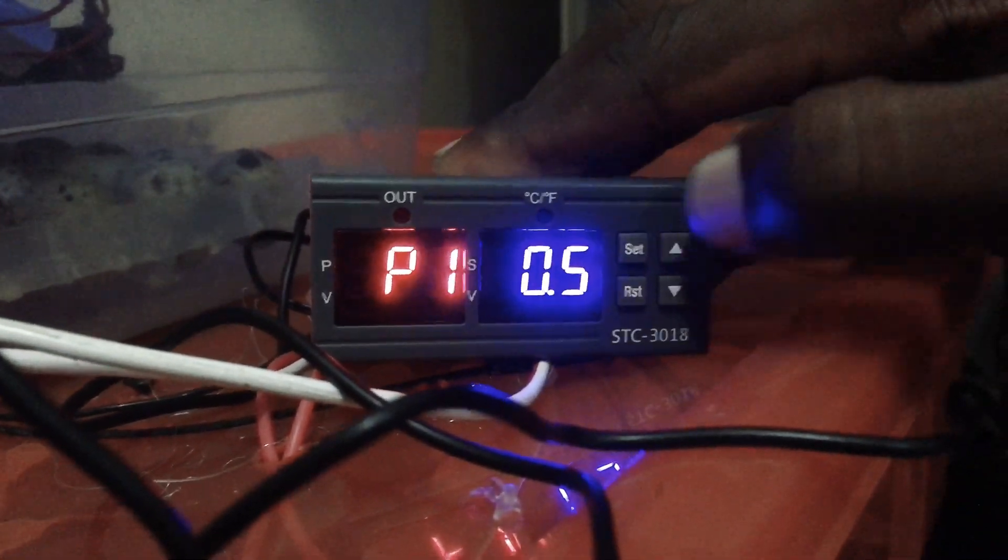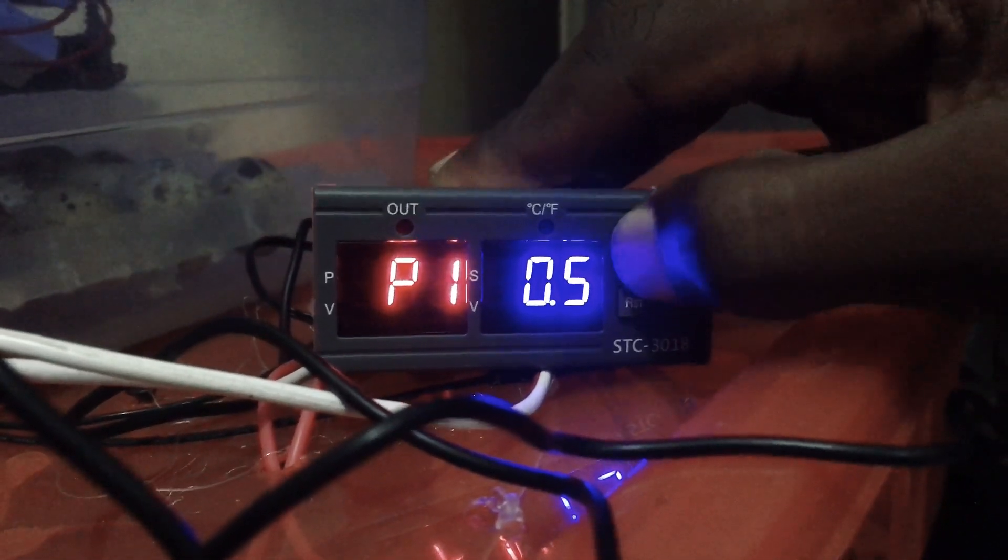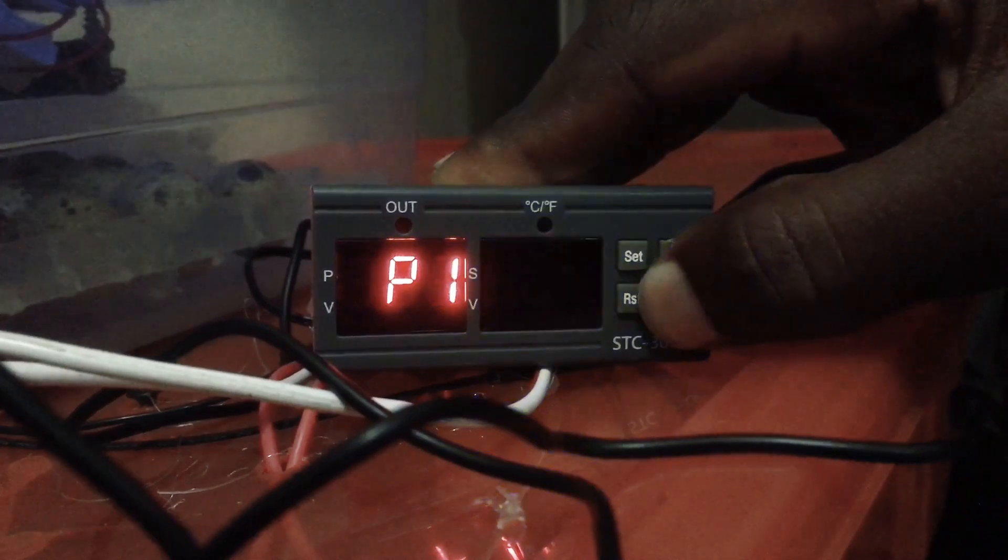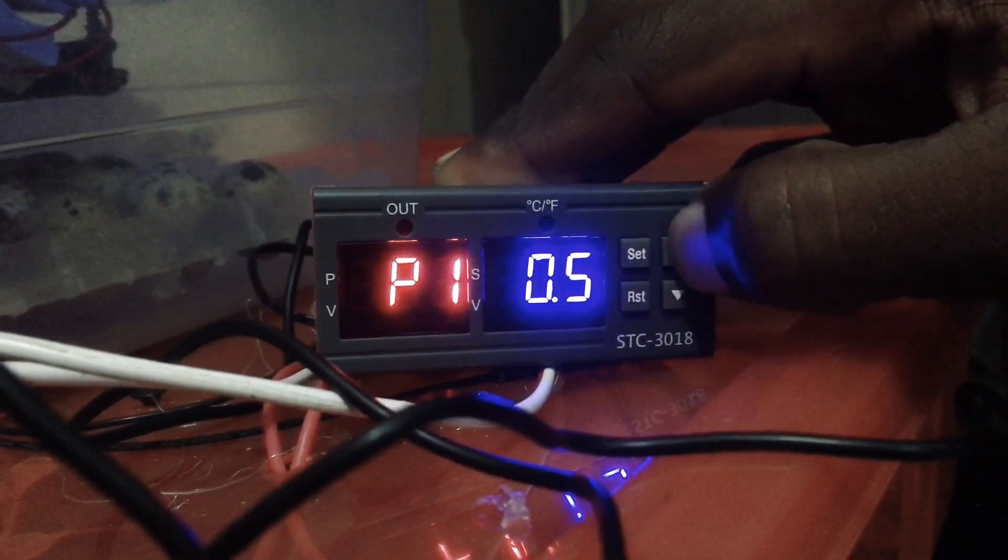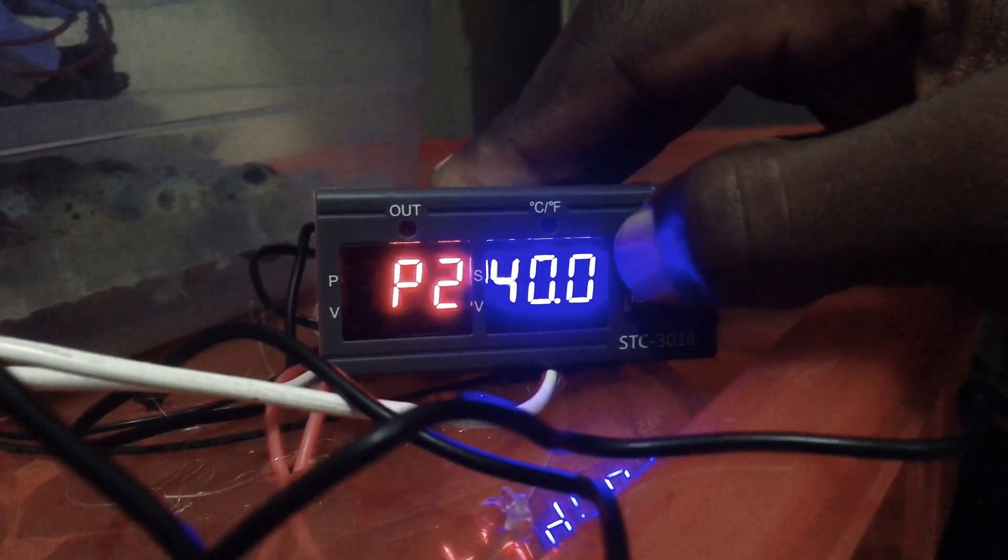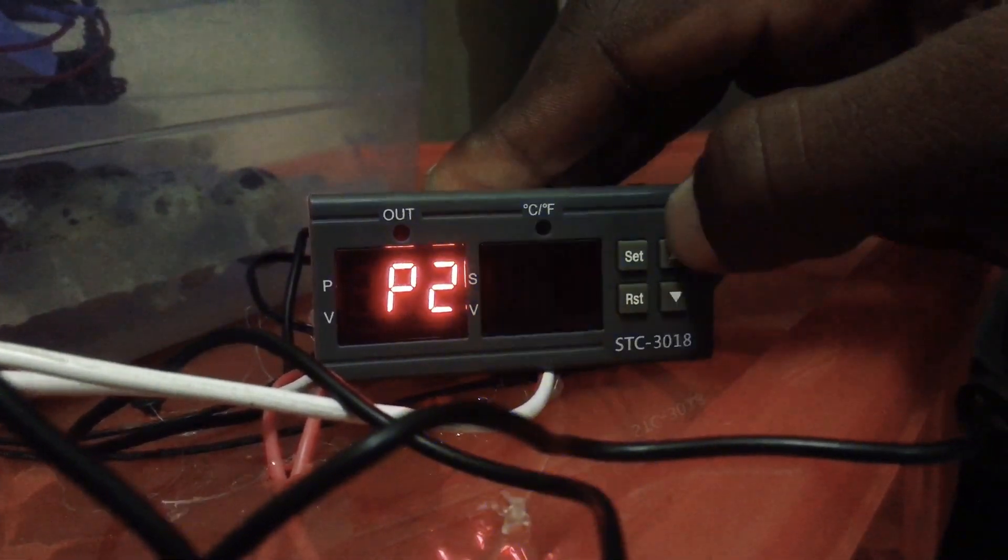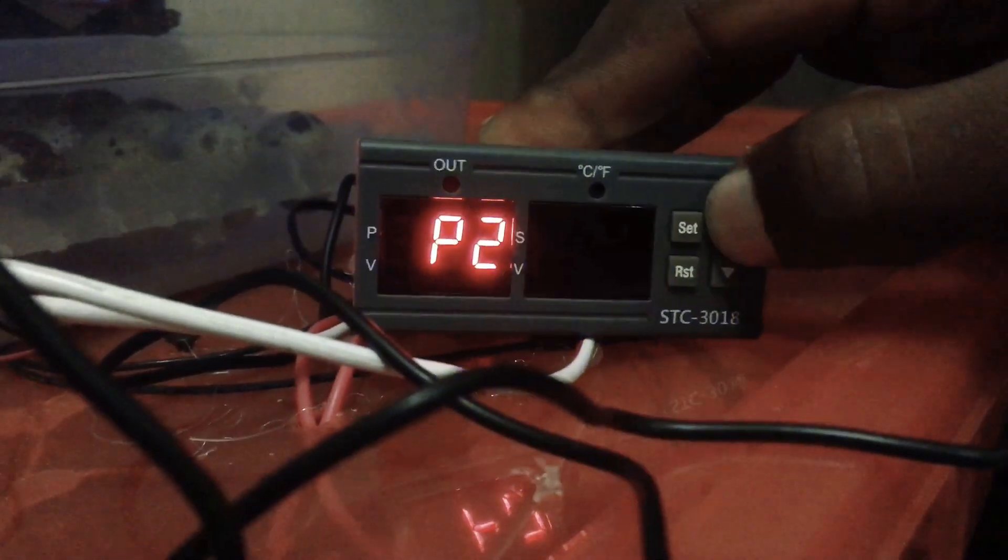You press set again, you press the arrow key up to change it to P1. P1 should be 0.5, so you set it to 0.5. You press set again, you press the arrow key up, you press set again, that's for P2. P2 should be 40.0.